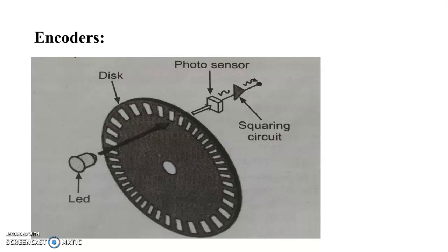Optical encoders are available in either incremental or absolute configuration for both rotary and linear motion. The optical encoder has an LED light source, a light detector, a code disc or wheel mounted on the shaft, and an output signal processor as shown in the figure. The disc has alternating opaque and transparent segments and is placed between the LED and detector, so it intermittently interrupts the LED's beam as it rotates.